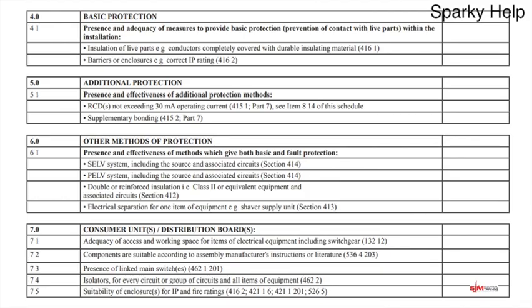So let's continue with basic protection on the next bit. Basic protection, as it says there, presence and adequacy of measures to provide basic protection. What it used to be called, which was much better, was direct contact. So basically what you're trying to do is prevent someone coming into contact with a live part. How do we do that? There are two main ways that we tend to do it, and those are the two that are listed here: insulation of live parts and barriers and enclosures.